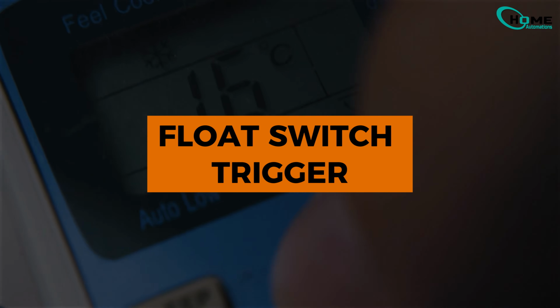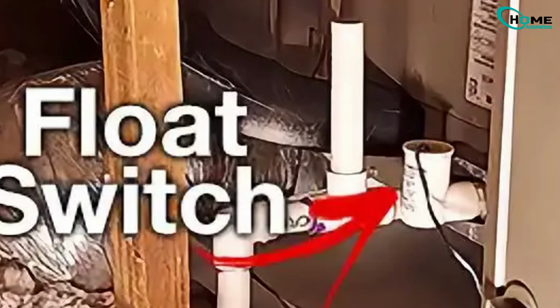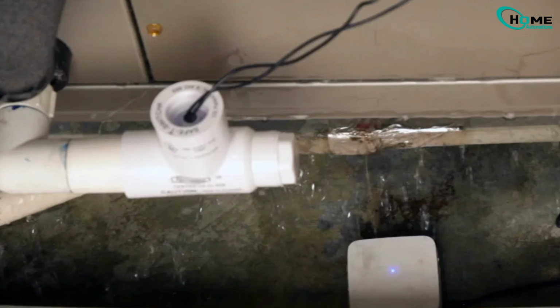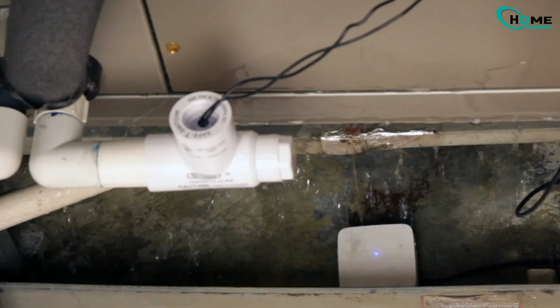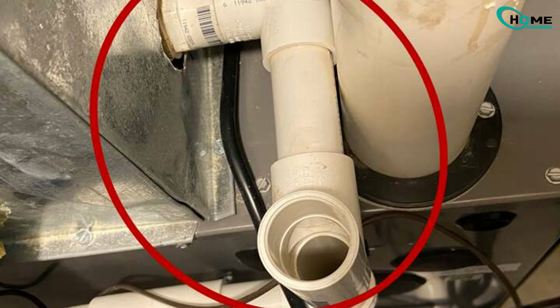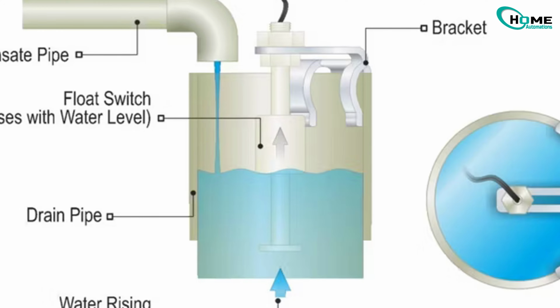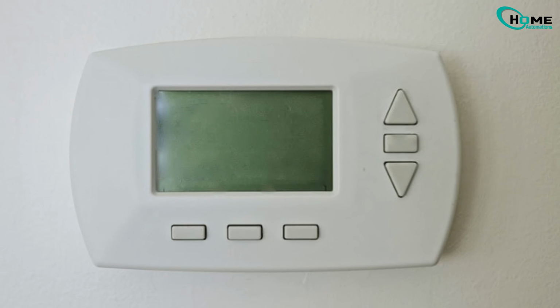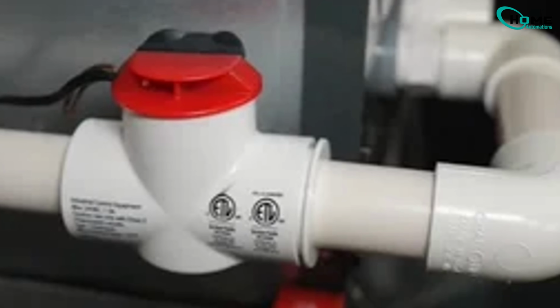1. Float switch triggered. Many HVAC systems have float switches designed to protect against water damage. If your drain pan is full of water or your condensate line is clogged, the float switch will cut power to the thermostat. This is actually a safety feature to prevent leaks from damaging your home.